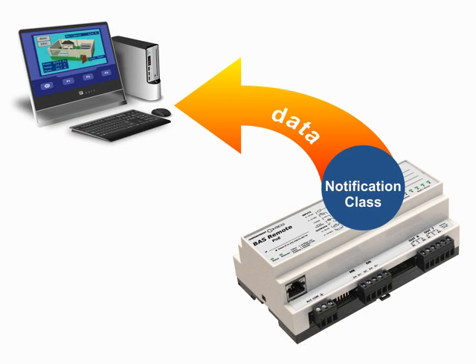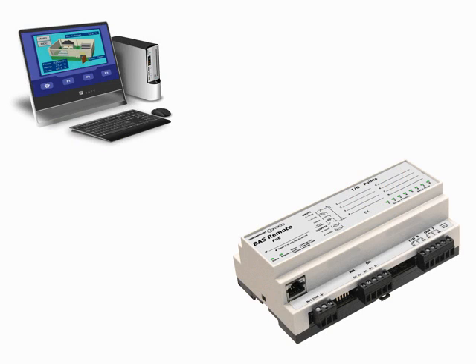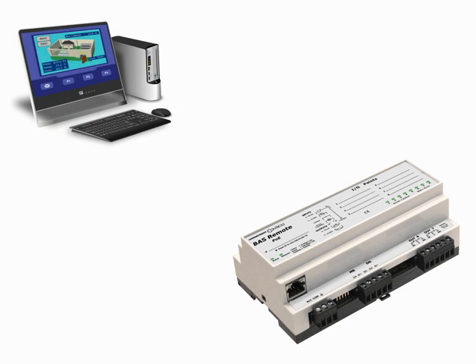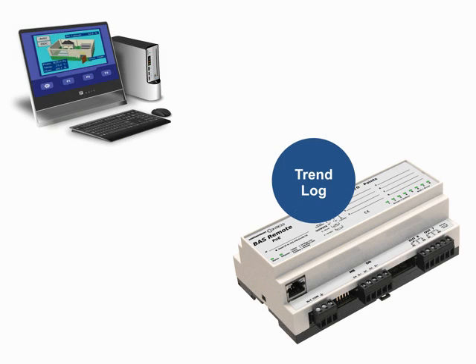Internal and external trending are supported. A client device can trend objects within its own device along with objects in other devices. This is called external trending. A server device may not be able to trend at all, or may only be able to trend its own objects. This is called internal trending.